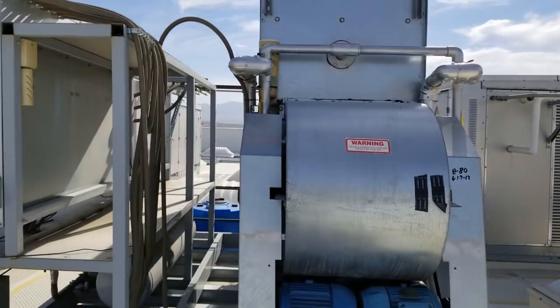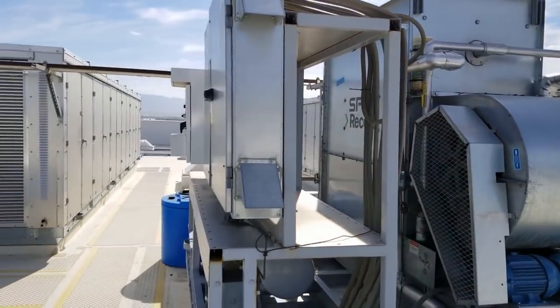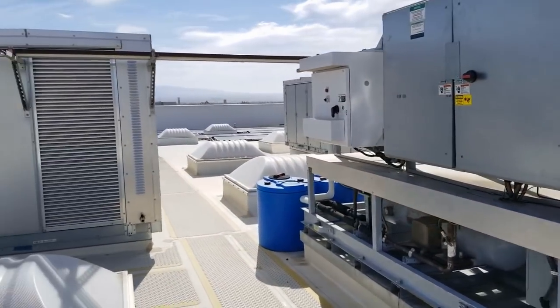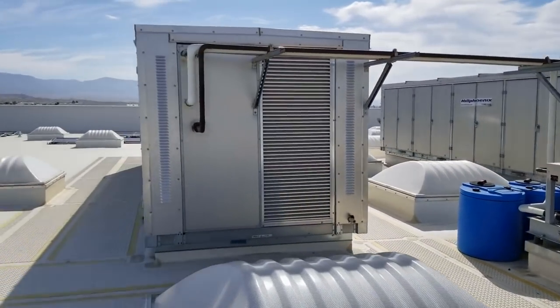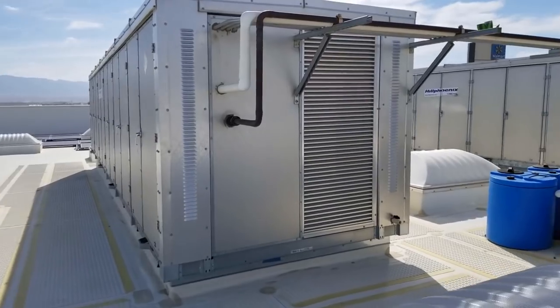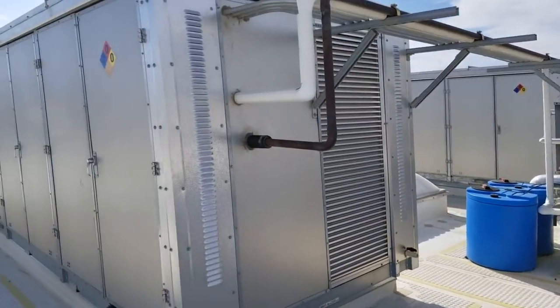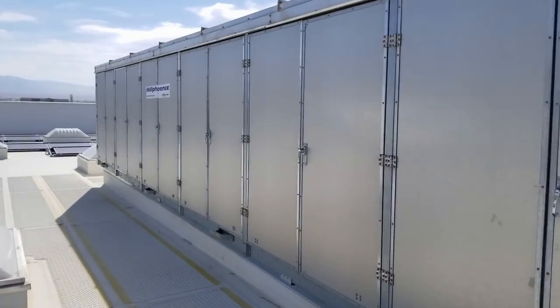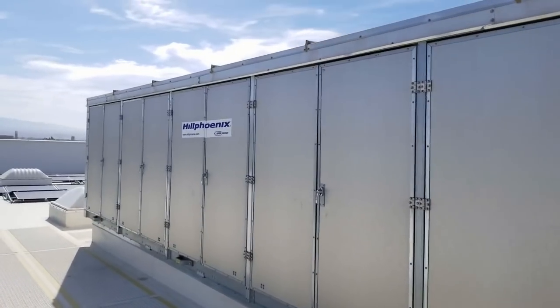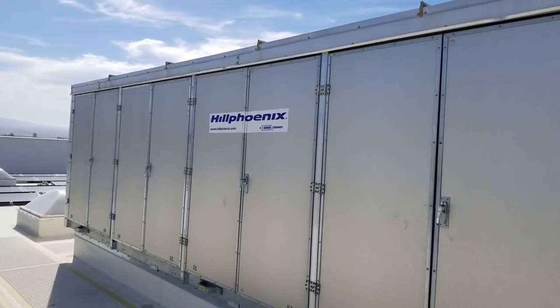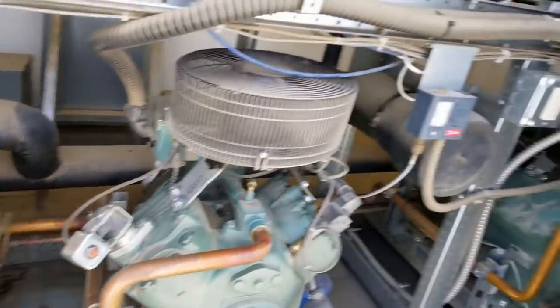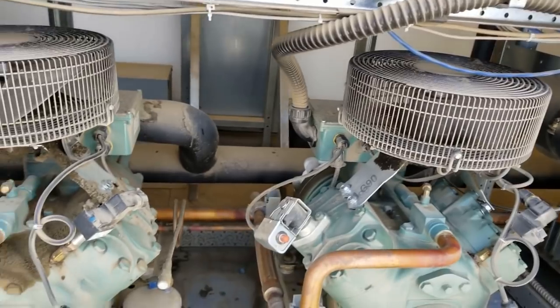And I got rack A, my low temp, which is CO2. I got a call for compressor A oil fail. So we're gonna get into this rack right here, made by Hill Phoenix, and we're gonna check it out, see what happened. So let me open this up and we'll get into it. Okay, got my rack open.